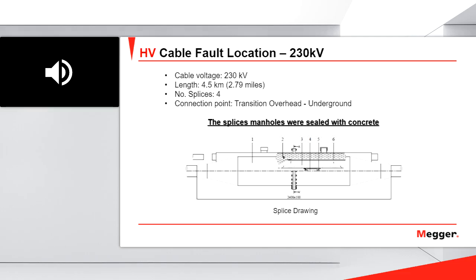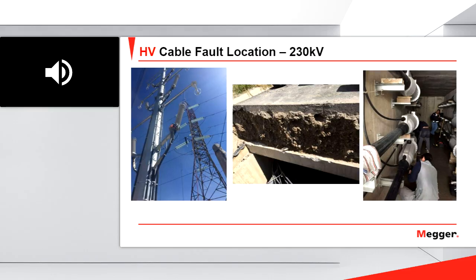The cable was, as I said, 230 kV. The length of the cable was 4.5 kilometers or 2.79 miles. We had 4 splices. This is the drawing of the splice, and here you can see the lineman who connected the test leads to the transmission cable. This is the tip, some of the layers of the cable. And then here you can see the low voltage trace.